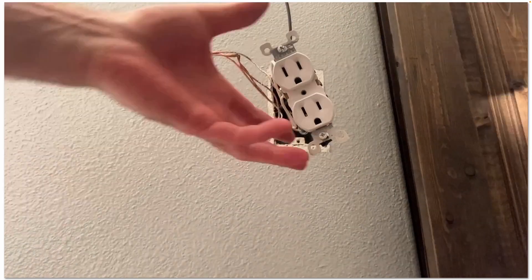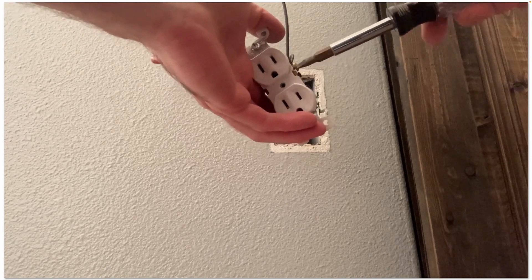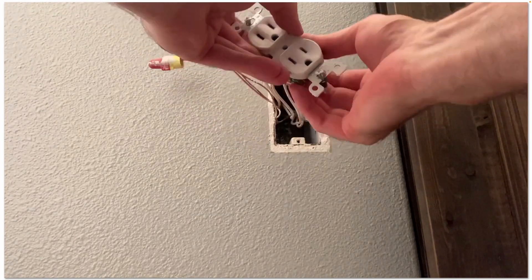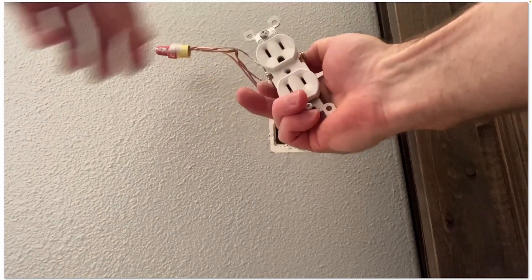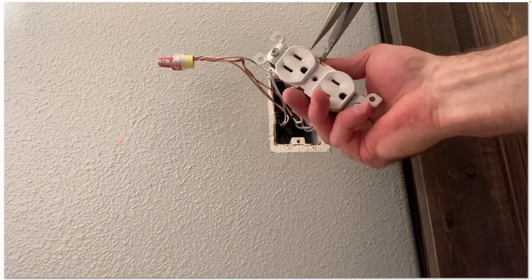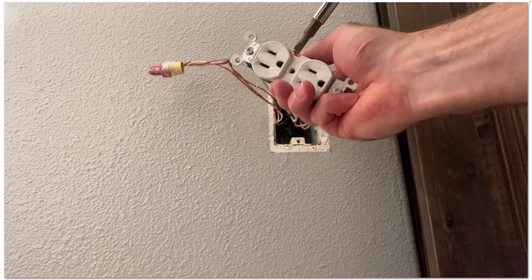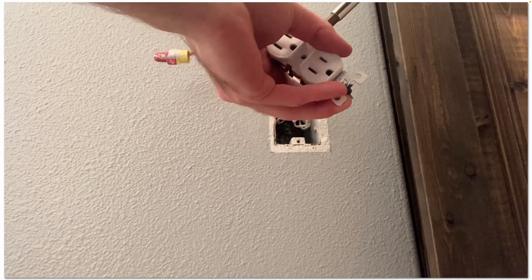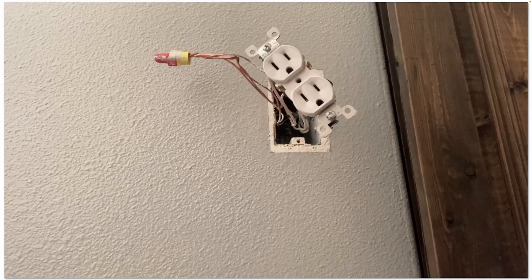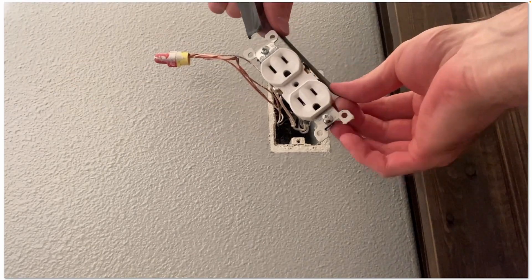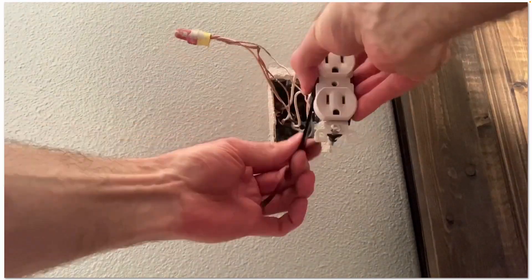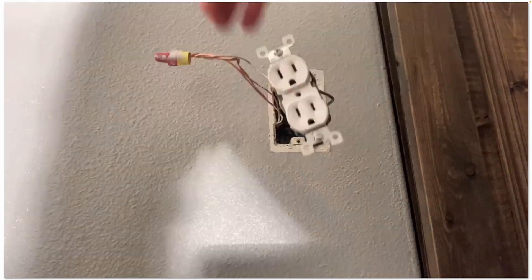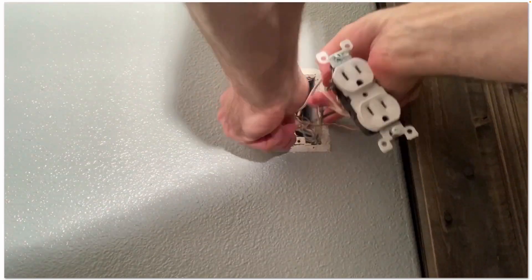Remember, white to bright, that silver colored screw, and then black to brass, the darker colored screw. Make sure you bend your loop in the direction that you're going to tighten the screws. And again for safety, I wrap electrical tape around all of my terminal connections on my switches and outlets as a best practice.